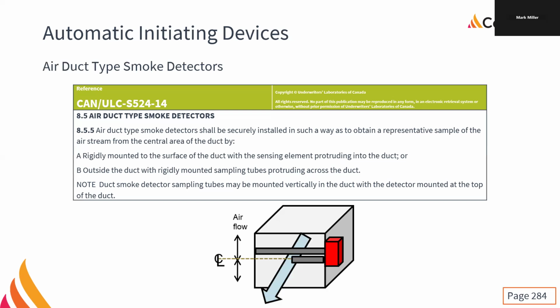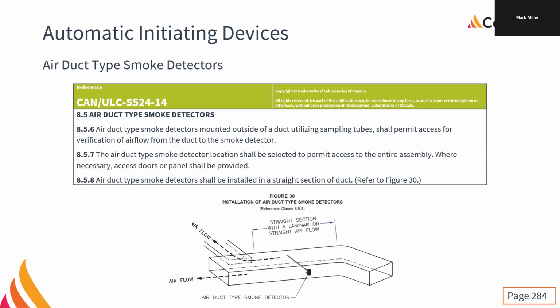Perfect. And then you have a short tube that just pokes into the ductwork like we see here, and it's open at the end, and the air flowing by actually sucks the air through the duct smoke detector. It's the Venturi principle. Works pretty cool. Yeah. So we need to have a straight section with laminar airflow because every time the air hits a corner, it gets very turbulent, and we're not going to be able to detect it properly.